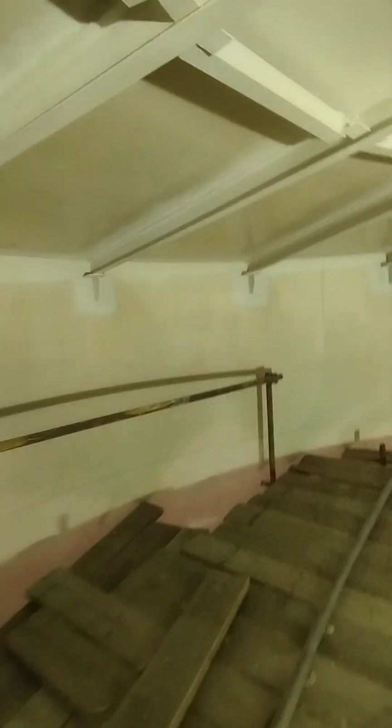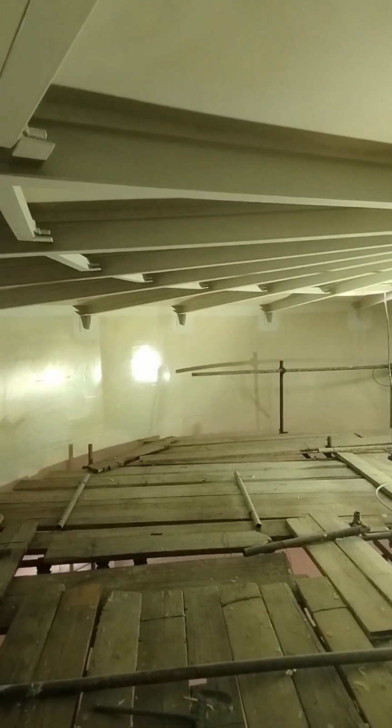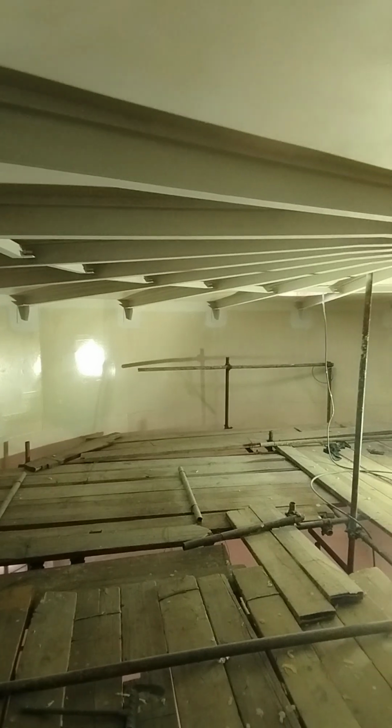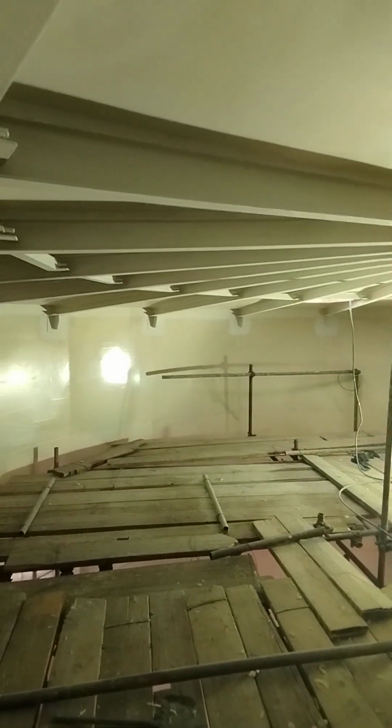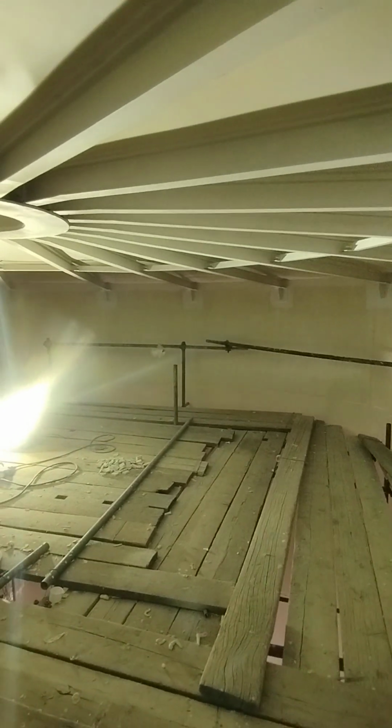This storage tank's duty is to hold about 500 cubic meters of demineralized water, whose pH is around 7. Demineralized water has some corrosive properties when it touches materials like carbon steel.